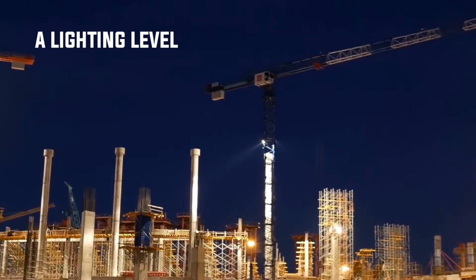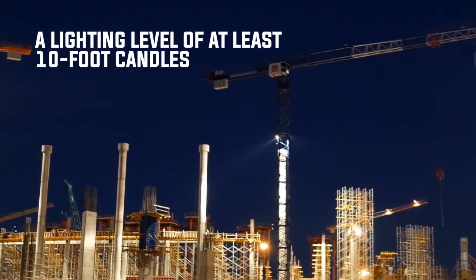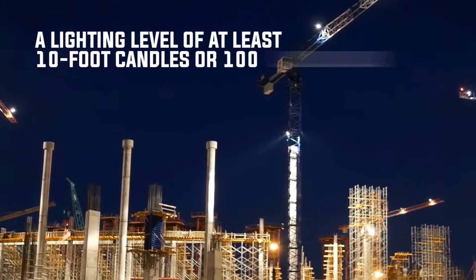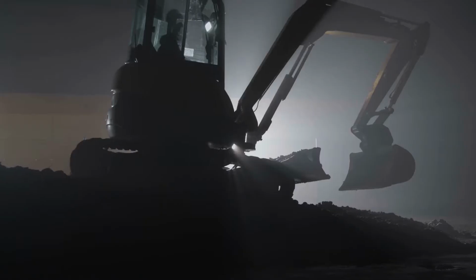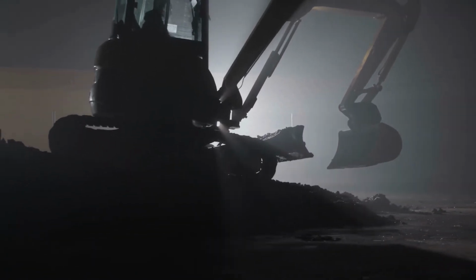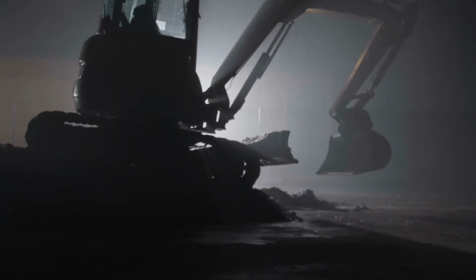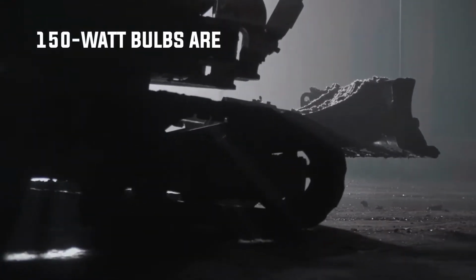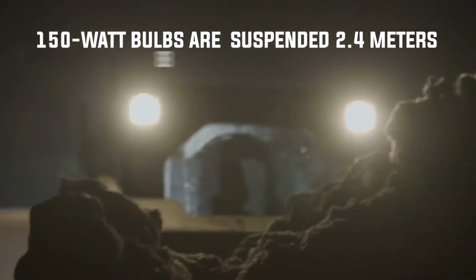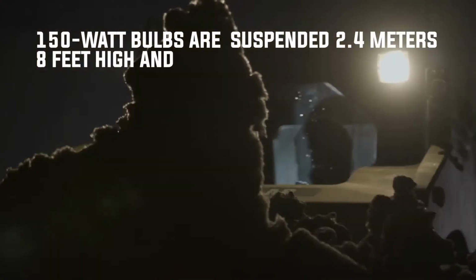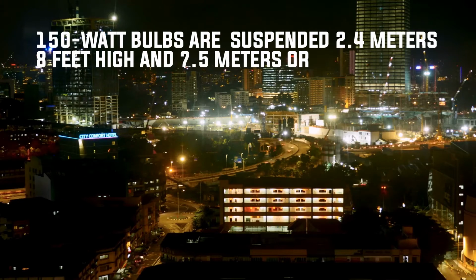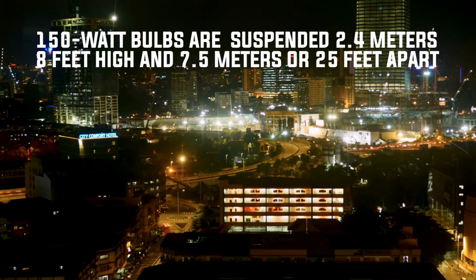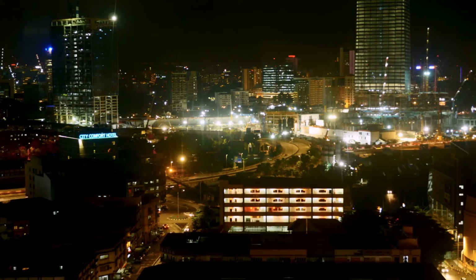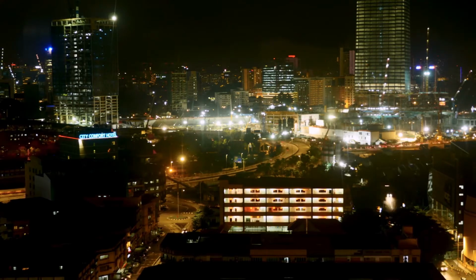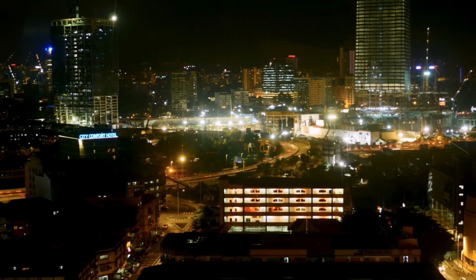A lighting level of at least 10-foot candles or 100 lux is recommended for general construction. Lighting levels should be at least 55 lux or 5-foot candles. That means 150-watt bulbs are suspended 2.4 meters, 8 feet high, and 7.5 meters or 25 feet apart, or suspended 3 meters or 10 feet high and 6 meters or 20 feet apart.